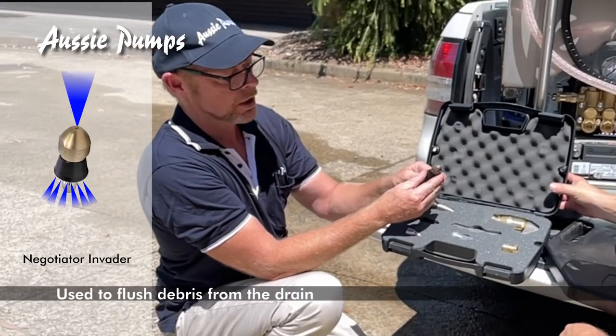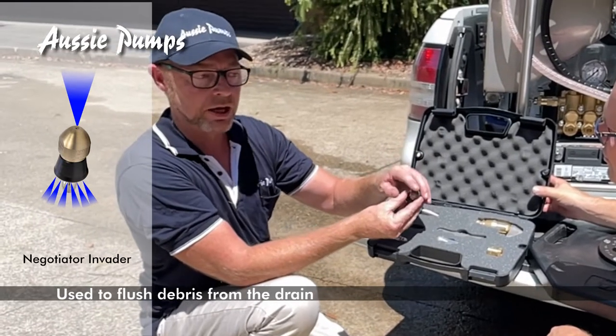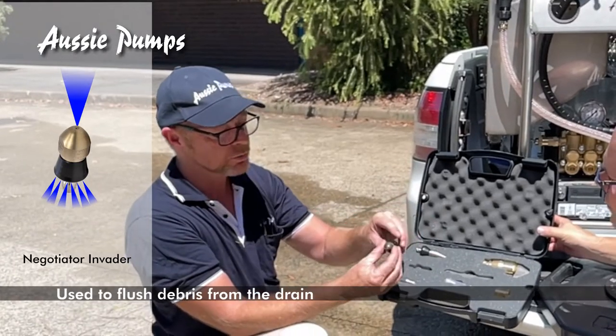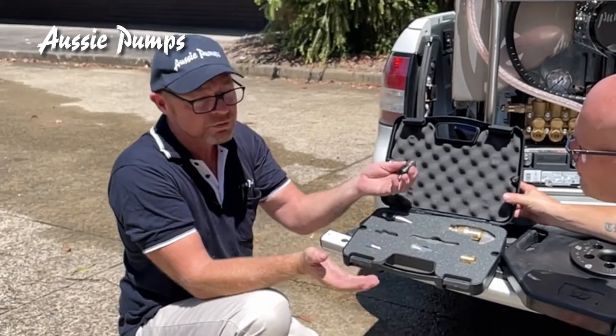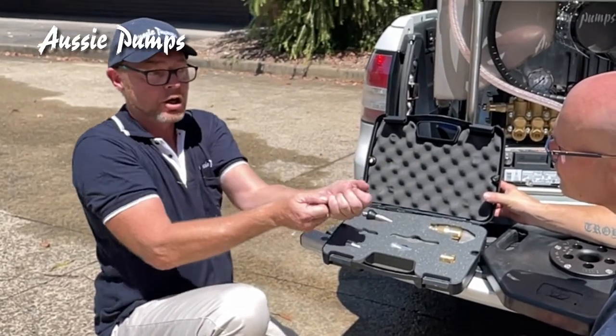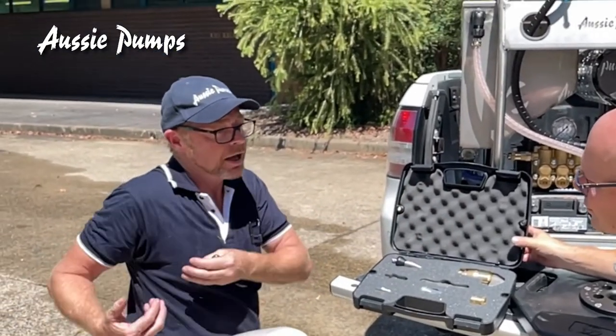The Negotiator Nozzle is a one-forward, six-rear configuration. It has less power at the front but more power at the back. This one is more used for flushing the pipe out. Say you've got a pipe that's full of sand, silt, or dirt — you put this on and as you pull your hose back towards you, you blow all the dirt and muck out into the pit.